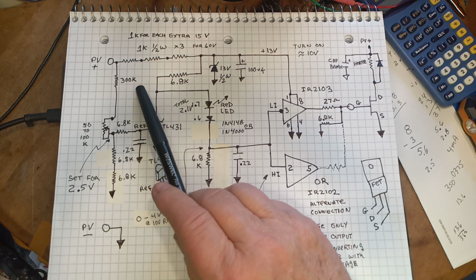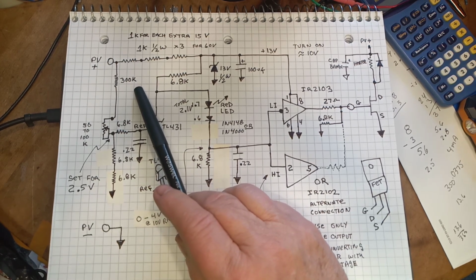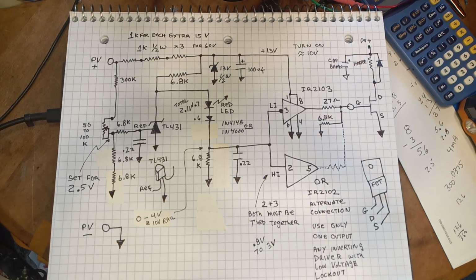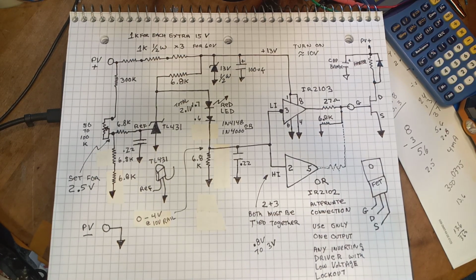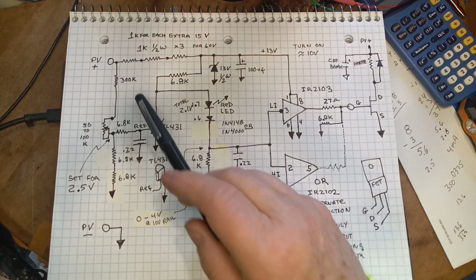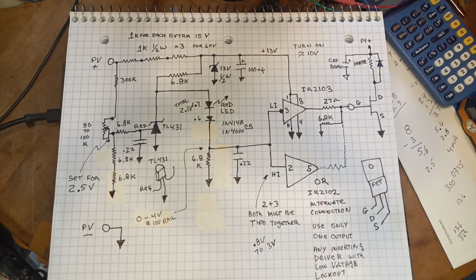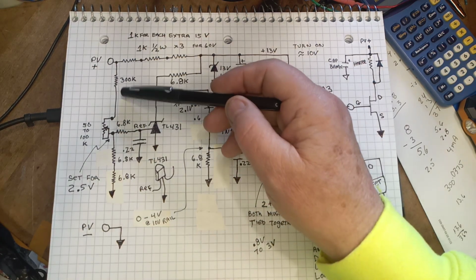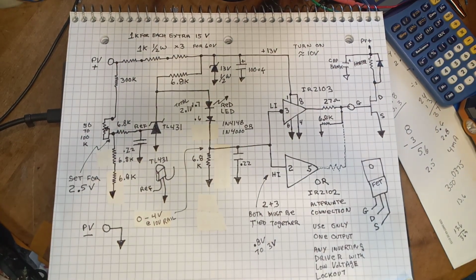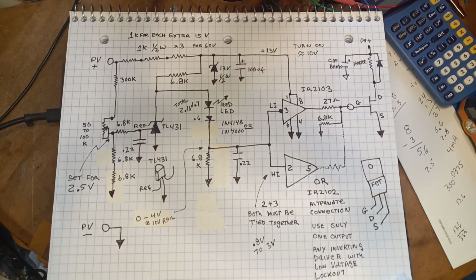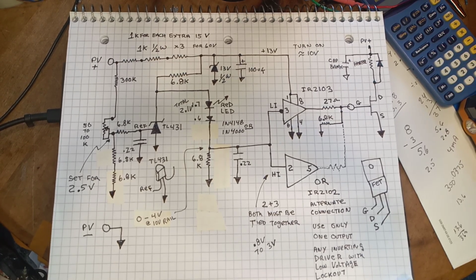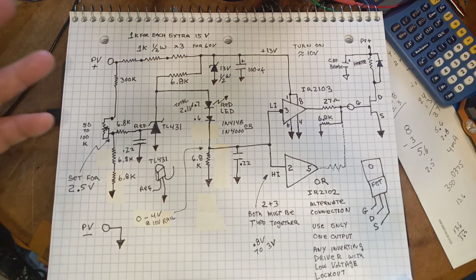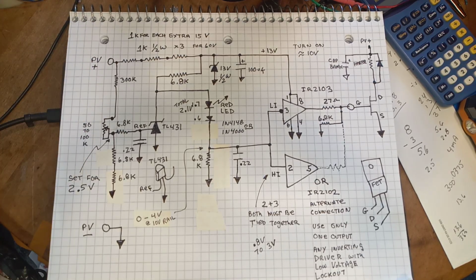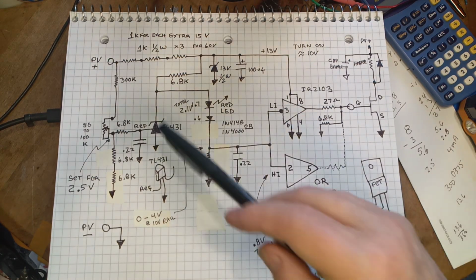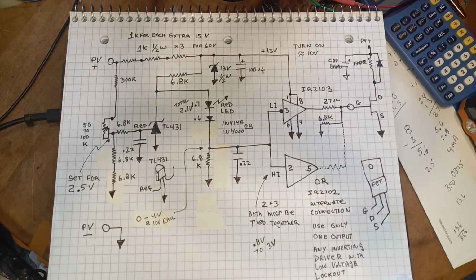I use a 300K because, quite frankly, I have a roll of 2,000 of these. They're special high voltage. They can take a 2 kilovolt pulse. And so a standard resistor would be a 270. If you're using regular resistors, I'd put 2 in series to have extra provision for a lightning strike nearby that might put a pulse on it. Most resistors break down at about 200 to 300 volts. So, yeah, a couple of those in series is always better.